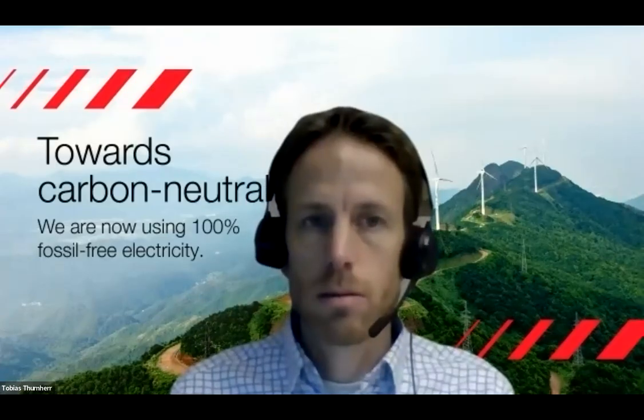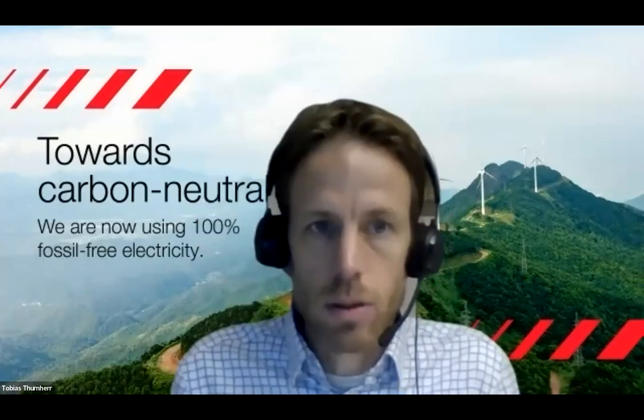Okay. Alan, it seems to me that the SFC allows conversion of voltage and phase as well as frequency. Is that correct? Yes, that's correct. Absolutely. SFCs have been used for a long time for feeding 16.7 hertz railway lines where a frequency conversion is needed. Unfortunately, the word is SFC, which is a static frequency converter, but we are not using the SFC as a frequency converter in the UK. It's just being applied to convert a three-phase voltage to a single phase with the same technology.